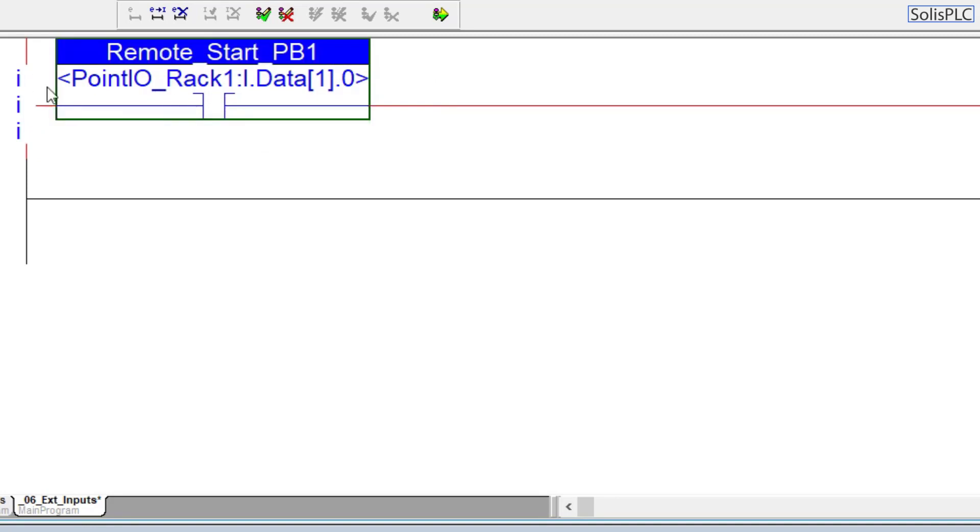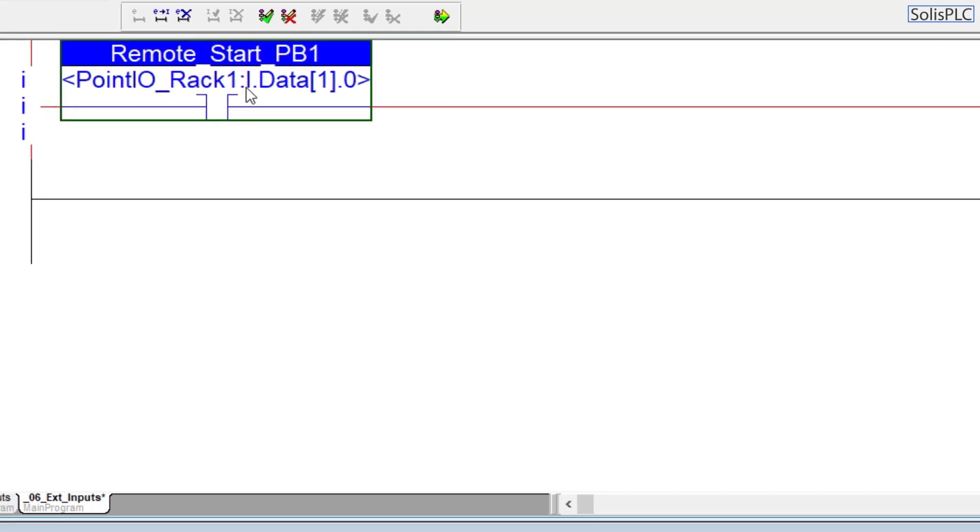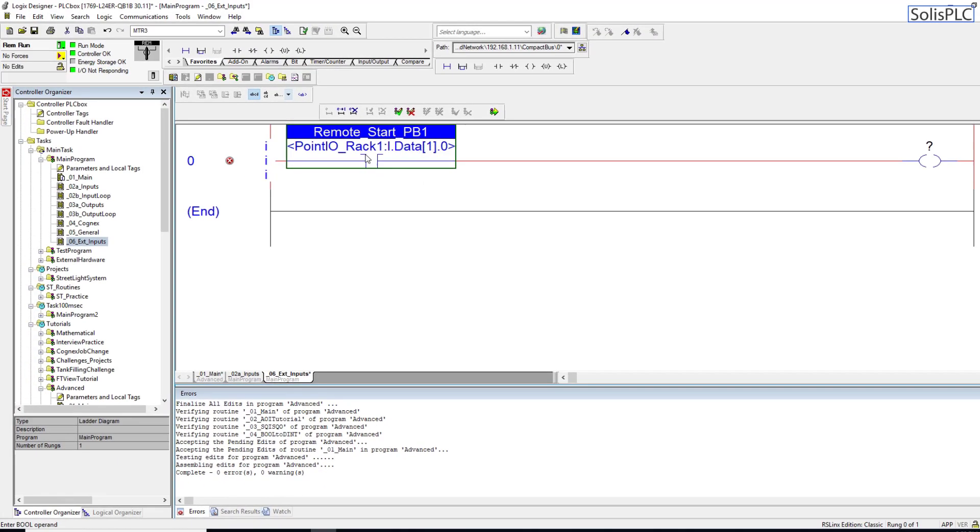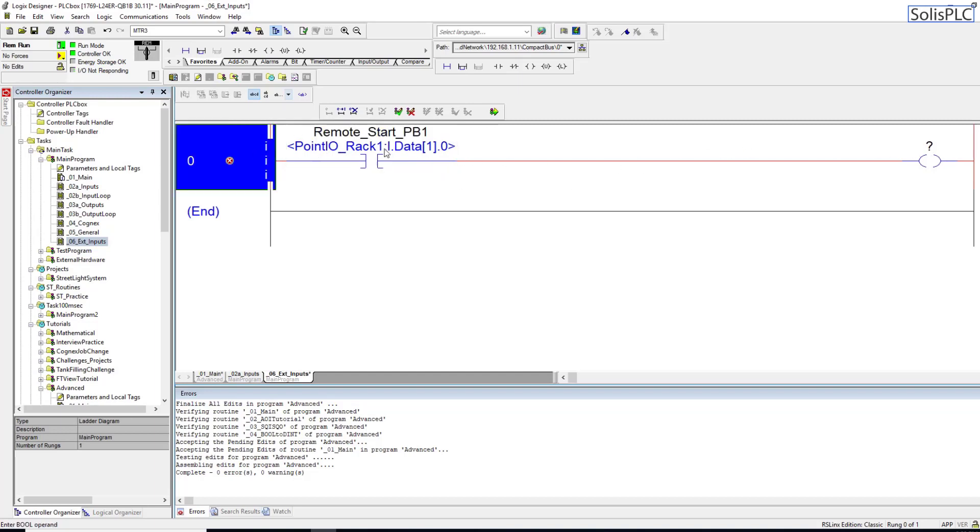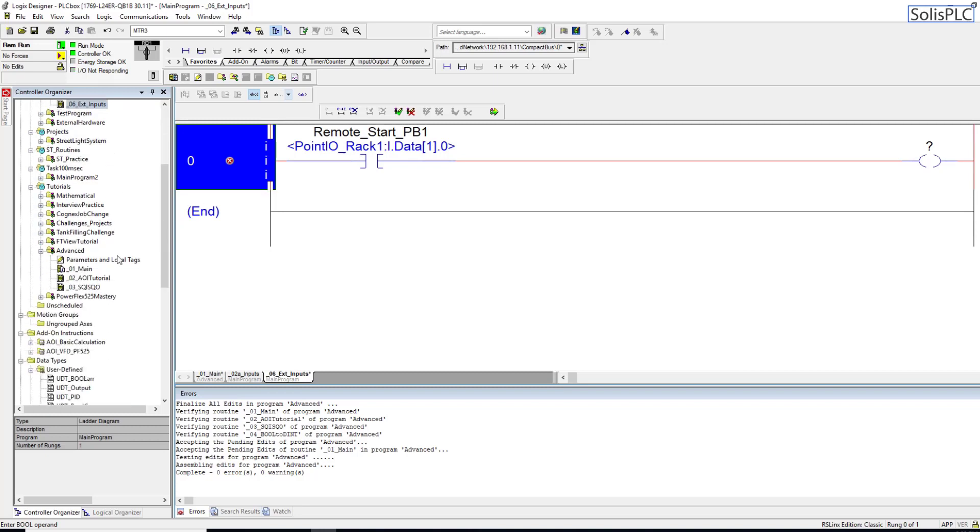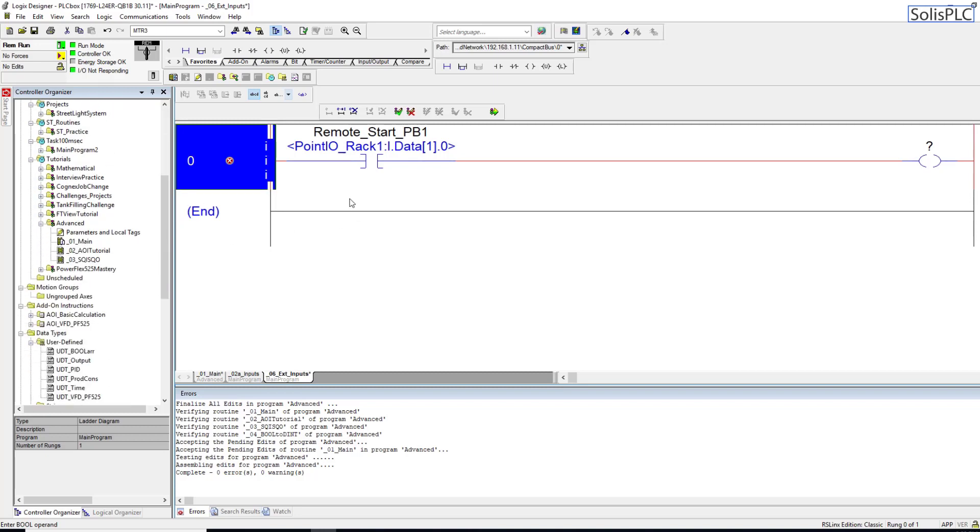What you will notice is instead of just having the pure name, we now have what's called an alias underneath this name. This alias represents the actual point which is going to be referenced by the tag. Think of this as a comment but it's the tag name, therefore you're creating a structure which is always going to be retained on the PLC side because this name is stored on the PLC even on version 20 and below.